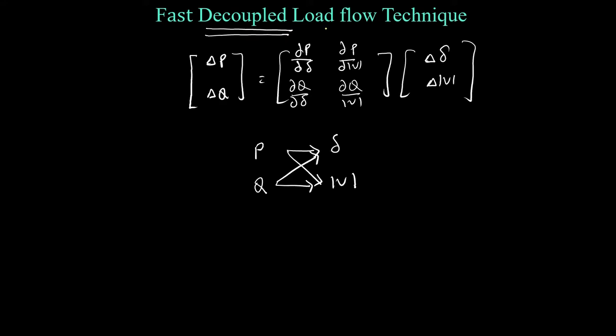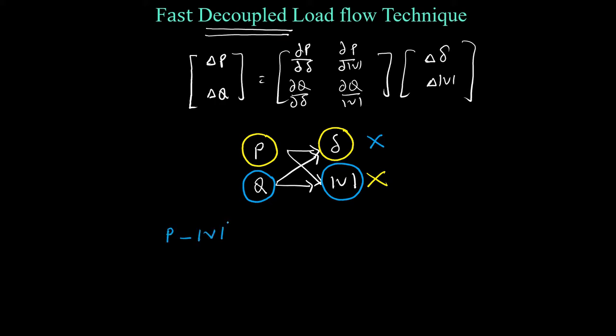In the Fast Decoupled Load Flow method, we say that real power changes are primarily governed by the phase angles, not by the voltage magnitude. Similarly, reactive power changes are primarily affected by the voltage magnitudes, but not the phase angle. This means there is a decoupling effect between real power and voltage magnitude, and a decoupling effect between reactive power and load angle.